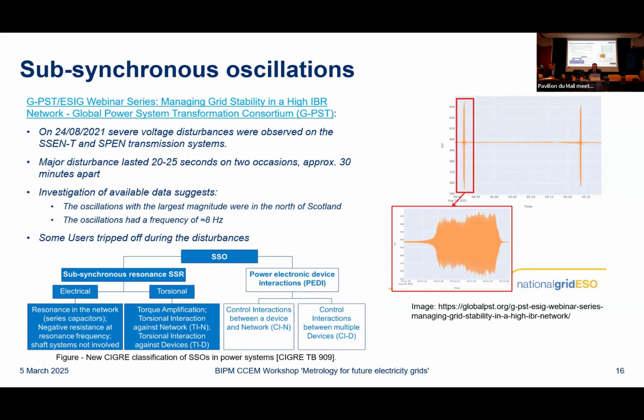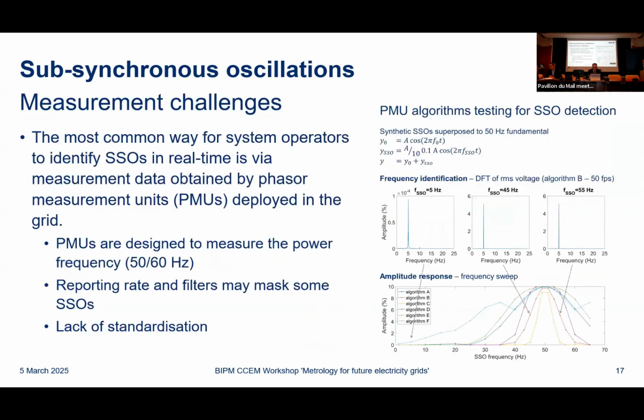But there are still some open questions as to how they can or should be detected and measured in the future. Obviously, they're visible using today's systems. Mostly people tend to use phasor measurement units to detect them, or they notice them through the amplitude variations. But a phasor measurement unit is designed to measure the fundamental frequency phasor, so it's usually at 50 or 60 hertz. And actually it has internal filters that try to suppress other frequencies. So while we can still see some of those oscillations in the phasor magnitude, there's a question as to whether those oscillations are being reflected properly by those types of instruments, or the way that they work nowadays.